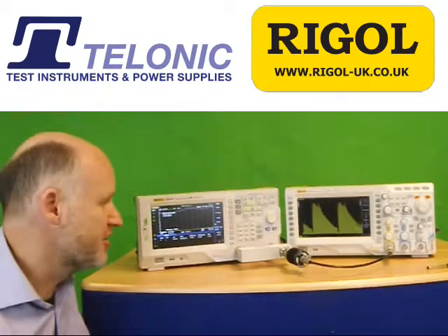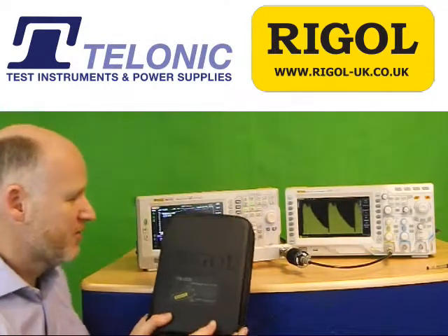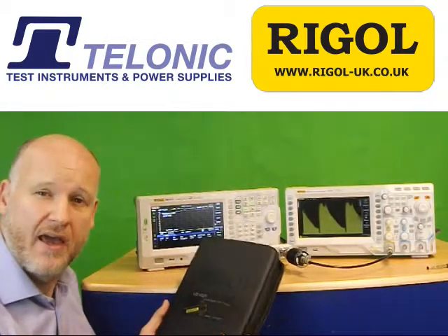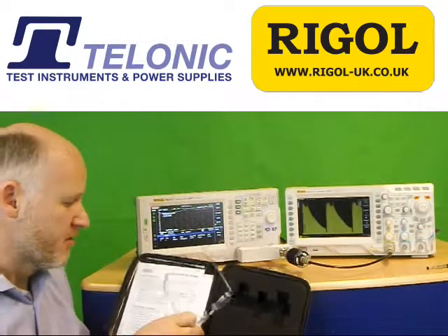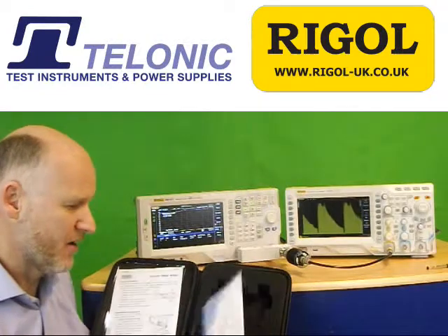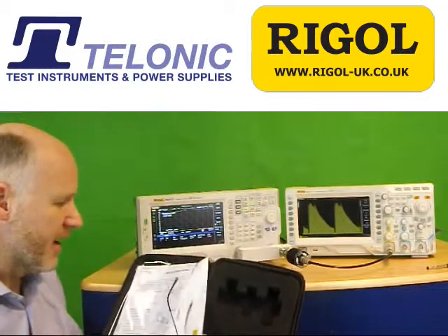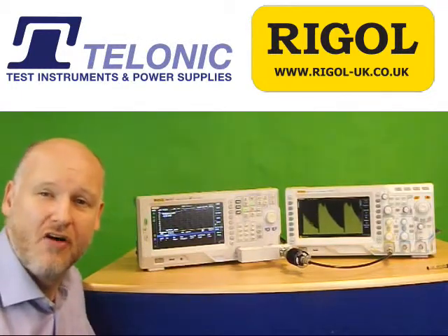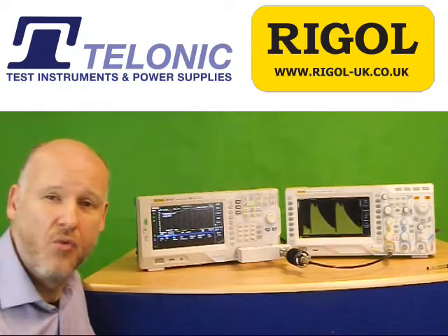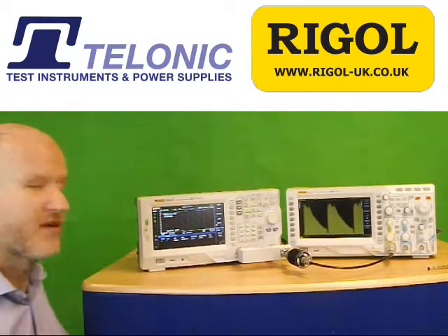What's special about today's presentation? I'm here to show you Rigol's VSWR kit. Right here we've got a beautifully packaged VSWR bridge that Rigol UK is offering with software that will run inside your Rigol Spectrum Analyzer. This software will provide a tabulated direct readout of VSWR ratio — for example, 1.15 to 1 on your antenna. I'm going to show you how to make those VSWR measurements.